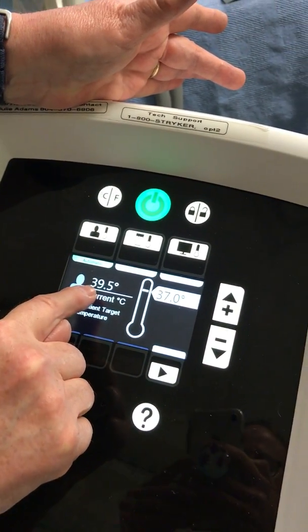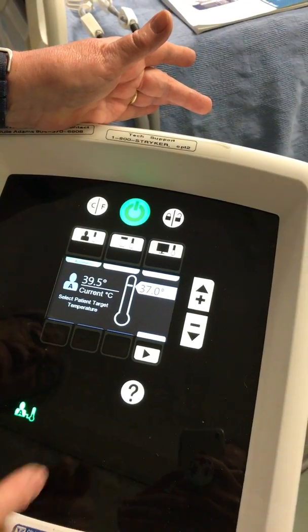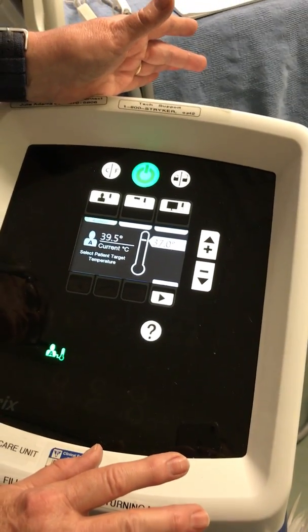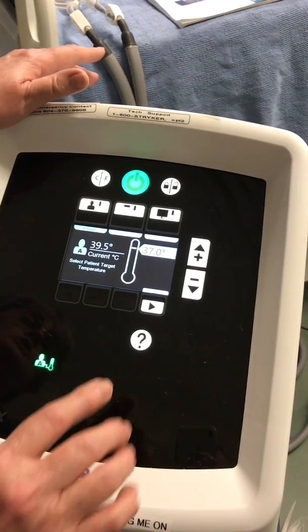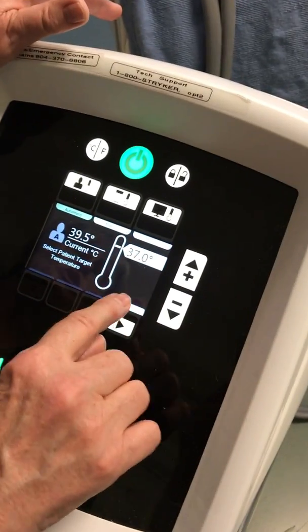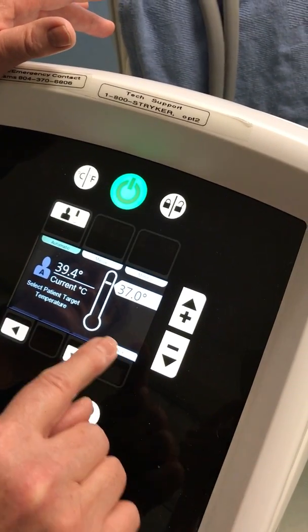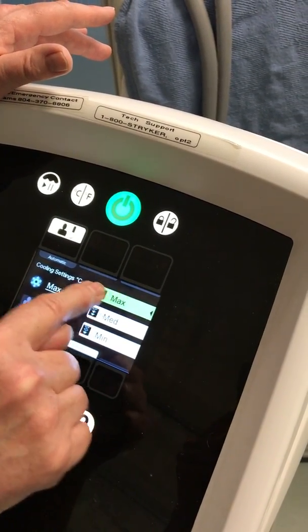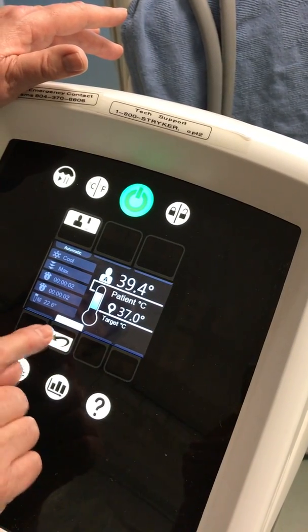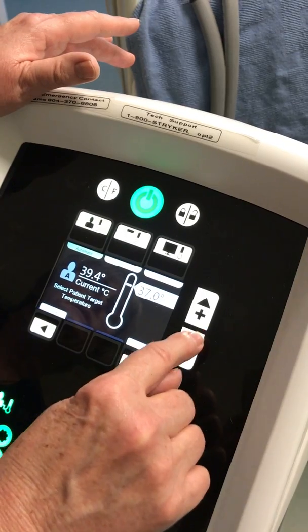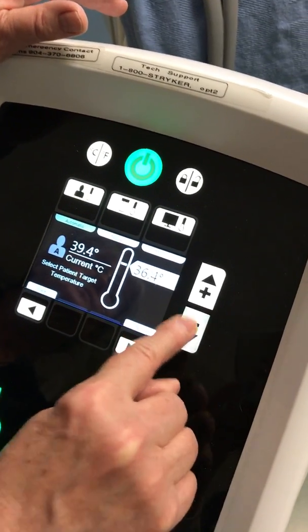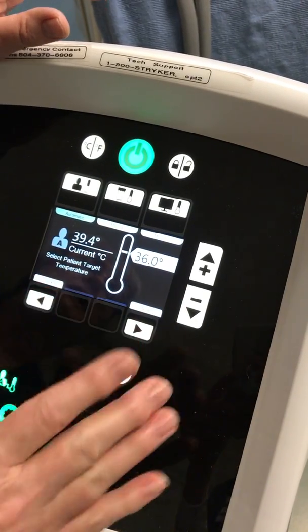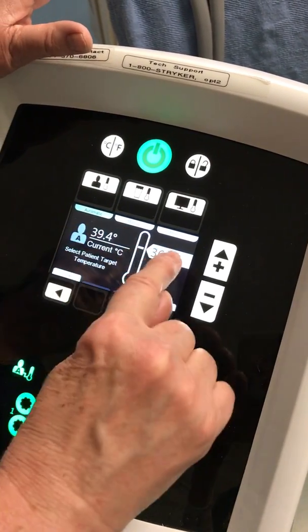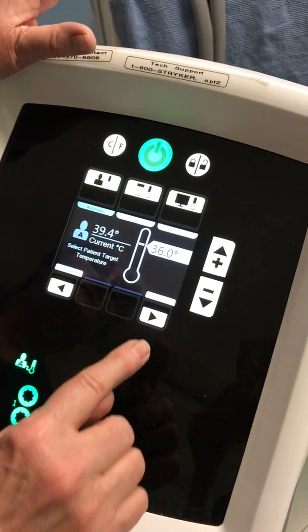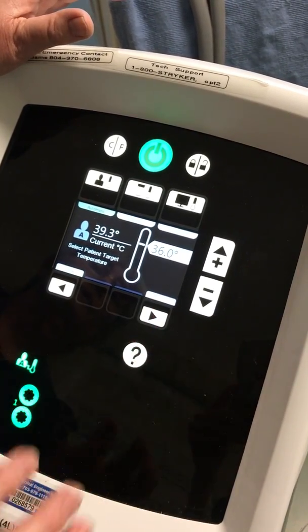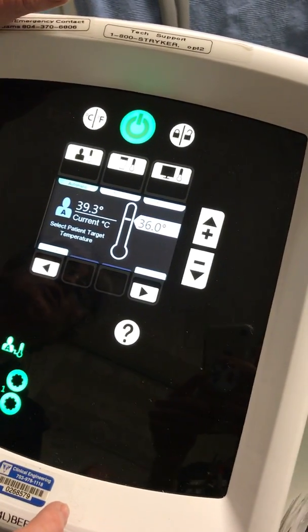And right now, it's showing the patient's temperature at 39.5. So we want to cool this patient. Let's say the doctor has ordered for the patient to go down to 36. So your target, this right here, you want to take it to the next level, and you want to check that. When you're cooling someone, you want to cool them as quickly as possible. So what we want to do is I want to lower this to 36, and this machine will cool them, monitor with the patient temperature and your target of 36, and it's set and ready to go.